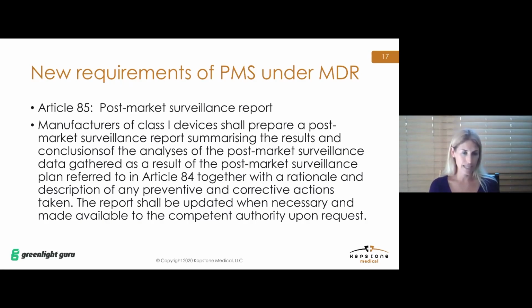It just needs to be updated when necessary, and it needs to be made available on request. So again, having a Class 1 device does not take away the requirement for performing post-market surveillance. However, in your plan, you can reduce the effort and burden based on that risk, so proportionate to the risk. And you're not required to provide the report to the competent authorities, but you do need to have a somewhat simple report covering your analysis and any conclusions based off the analysis, as well as any actions taken. And those just need to be available on request.